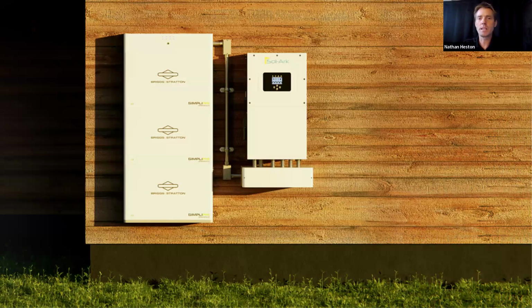But this is a nice version of what it would look like if you installed the inverter and battery outdoors, as you're welcome to—it's outdoor rated. It's shown here with a wire gutter underneath. Typically you'd use maybe a 12 by 12 wiring gutter or a 10-inch wiring gutter, then offset it off the wall with some strut. The Sol-Ark is 12 inches deep, so you need to make sure you've got room to land those drops.